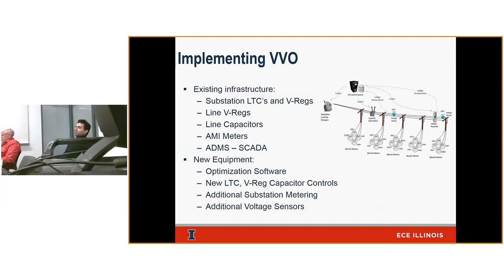It's a closed feedback loop: the system reduces voltage, then goes back to check AMI for violations. If no violations, it looks for further reductions to achieve more savings. The infrastructure for voltage optimization includes LTCs, line voltage regulators, capacitors, AMI meters, and our SCADA system that brings back and compiles all that information, giving the intelligence to figure out what voltage should be across the circuit in real time.